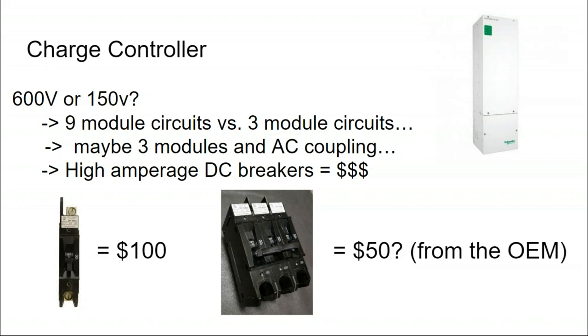That's fine, but then finding high voltage DC breakers becomes an issue. Here's a 100 amp DC breaker. This is an 80 amp charge controller, it needs to go on a 100 amp breaker. This 600 volt, 100 amp DC breaker, Schneider's trying to charge $100 for. So I ended up finding the original equipment manufacturer, and found a triple ganged breaker to get me three single pole breaker connections on three charge controllers for $50 instead of $300. But that's where, when you get into doing the DC side of the design thinking you're optimizing something or gaining points technically, your access to DC side balance of system equipment evaporates rather quickly.